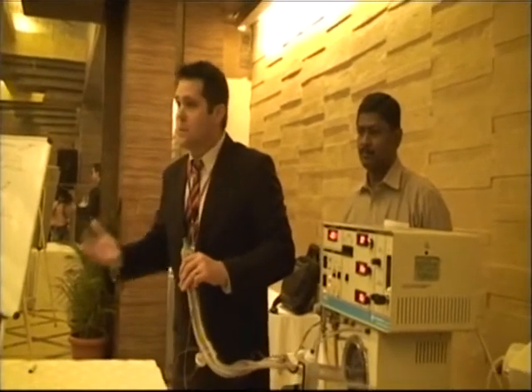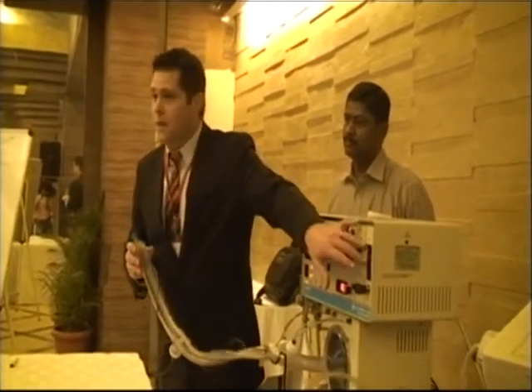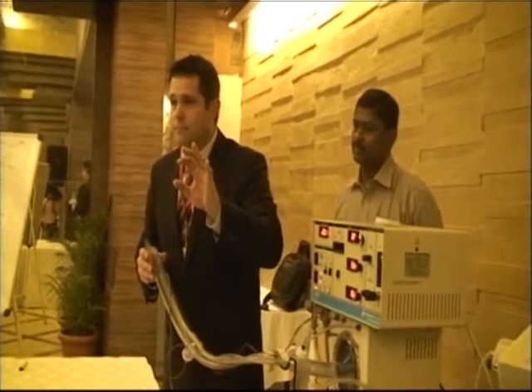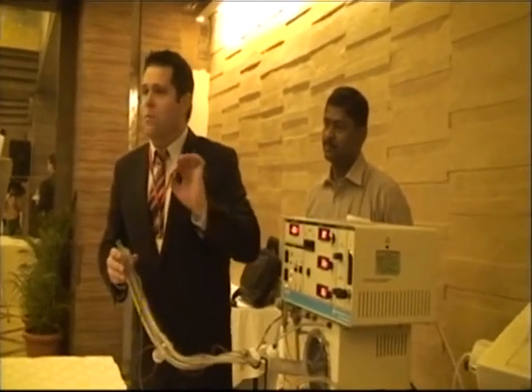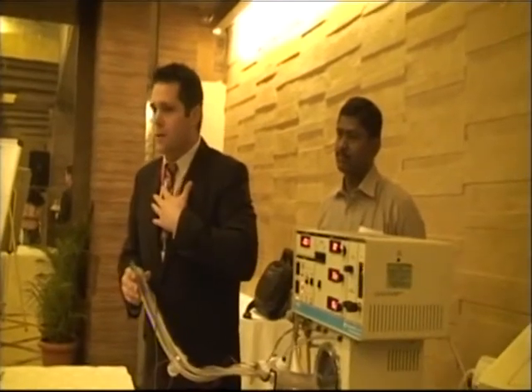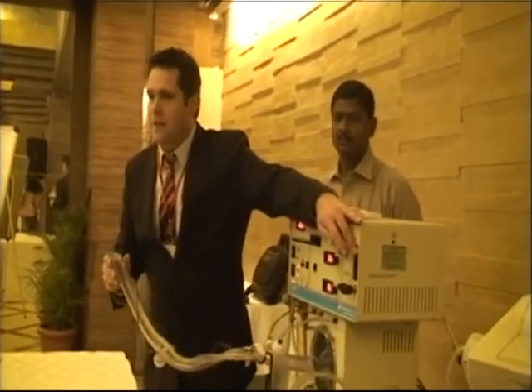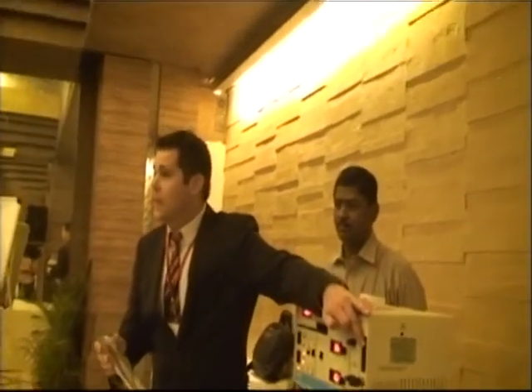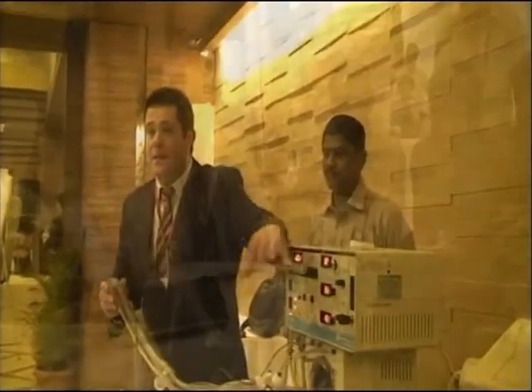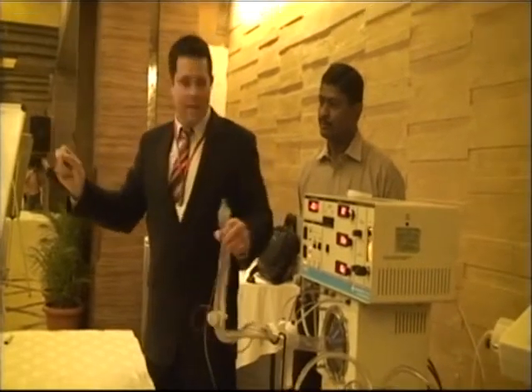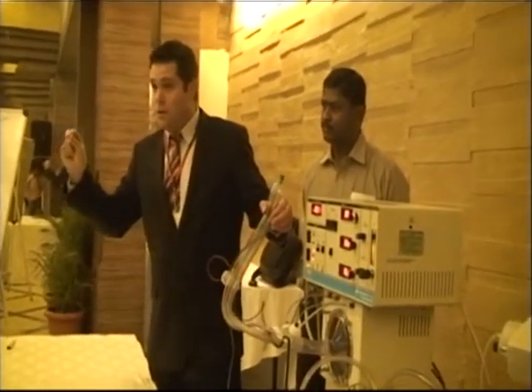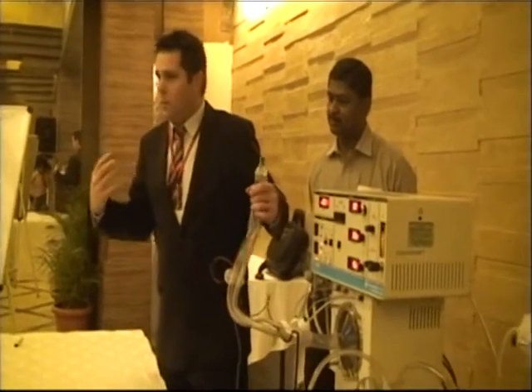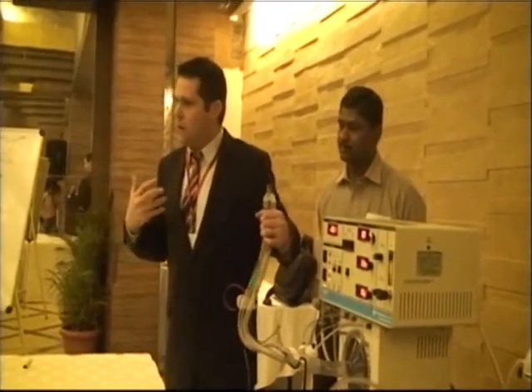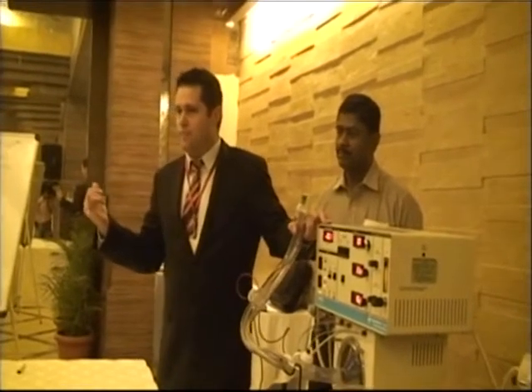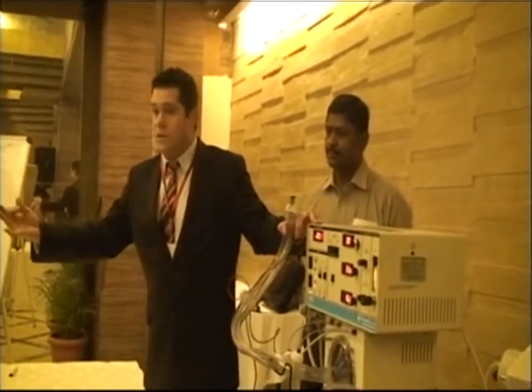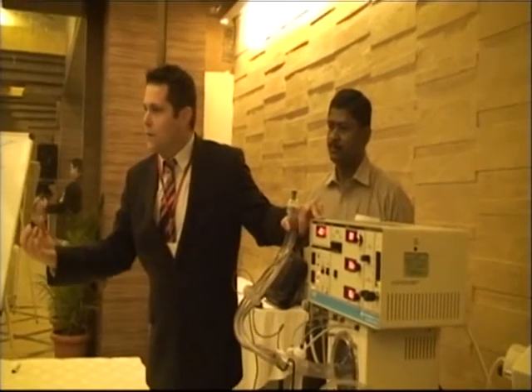Now, if the baby wakes up and is breathing, you may need to increase that bias flow a little bit to keep that pressure constant. Otherwise, the alarms will be going off, and you won't have a stable mean airway pressure being provided to the lungs. So the bias flow, generally speaking, is 10 to 20 liters a minute. Larger patients, you need that higher bias flow to maintain. We're going to make adjustments in that CPAP, or the mean airway pressure, to try to enhance lung recruitment. We want to try to optimize and maintain the lung volume, and that's all going to be based on X-ray. It's going to be based on PaO2, saturations, and the amount of FiO2 that the infant requires.